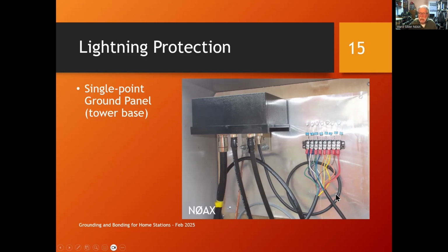And now I'm going to save you some serious money. And everybody's like, what? He's going to save money? Okay, so instead of that fancy rotator control cable with the 2 number 16s and the rest of them are number 18, it costs like $1 a foot now or more, go out and get irrigation system control cable. This is a 10 conductor, they're all number 18, multi-conductor cable. It's in a PVC jacket here that's rated for direct burial, and you can double up 2 pairs to make those heavy pin 1 and pin 2 solenoid connections on the standard rotators.